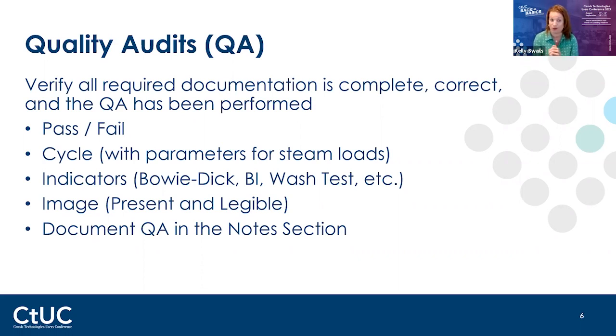It's something you can help them with. Next year, look at that cycle. Make sure there's a cycle. So if it's a washer, it's your wash cycle, or it's your decontam descaler cycle. So different things that you maybe have in there. And if it's steam load, make sure you have parameters. You have to make sure you have parameters with all of your steam.